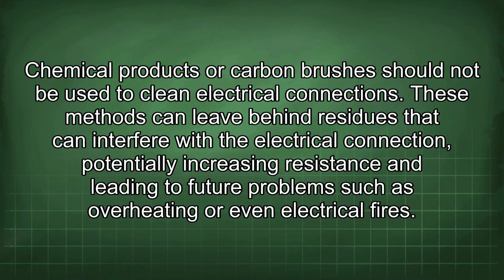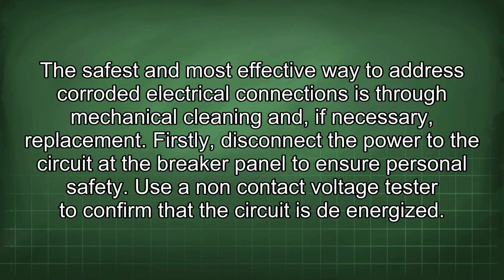Chemical products or carbon brushes should not be used to clean electrical connections. These methods can leave behind residues that can interfere with the electrical connection, potentially increasing resistance and leading to future problems such as overheating or even electrical fires. The safest and most effective way to address corroded electrical connections is through mechanical cleaning and, if necessary, replacement.